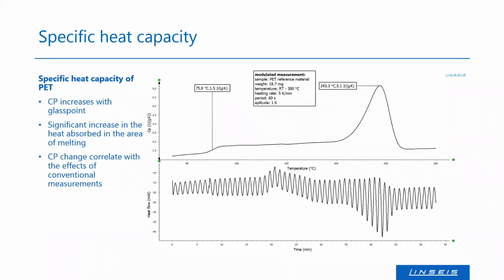And of course, this correlates with the amplitude of our raw signal below. During the glass transition, the amplitude gets higher. At the recrystallization, we can see in the raw signal that the amplitude is constant, and for this reason, we cannot see it on the CP signal. And then during the melt, of course, much heat is needed to heat the sample up. So here, the amplitudes are extremely high, and later, it's lower again. And also on the CP signal, we can see here the CP of the liquid is lower than the solid before.